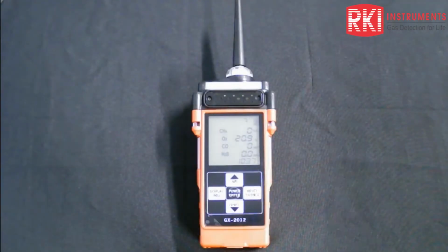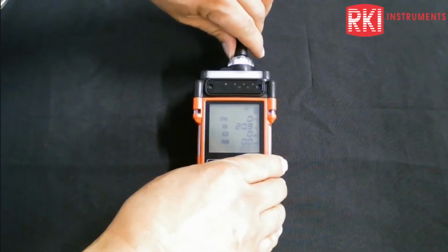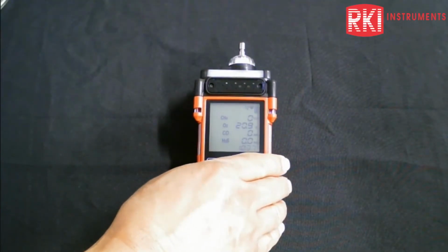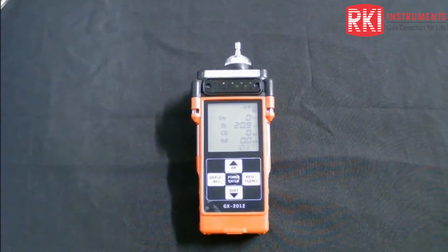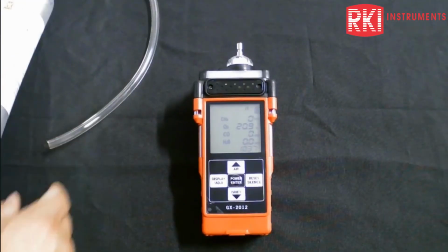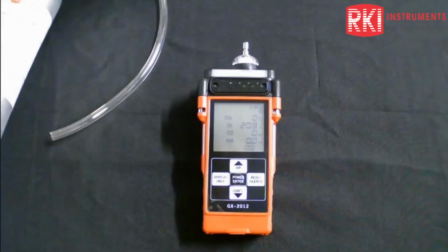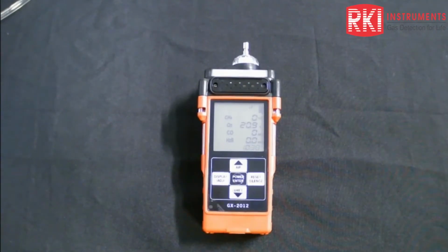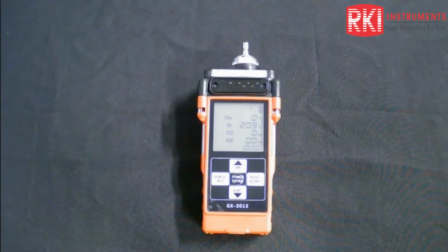Hey, John, I want to also add this, if you could. I would like you to apply the 4-gas calibration standard to the unit. Sure, I want to show them how it will react, and I'd like to set the unit into its alarm state. Okay, I would like you to show them how you can silence those alarms, so they understand that when they're working with it they can silence the alarms but still know they're in a potentially hazardous environment. Yeah, you don't have to do that, I already did that for him. Oh, you did? Okay. Did you also show them the percent by volume? No, I haven't got that far yet. I was waiting for you. Okay, all right. Hey, John, we'll do the percent by volume next. Show them how it auto ranges. Okay, so we'll do that next.